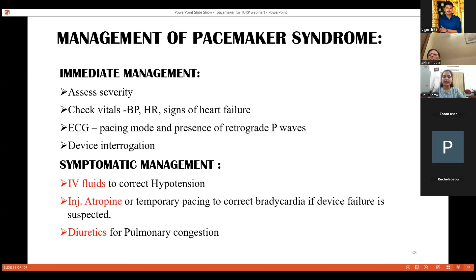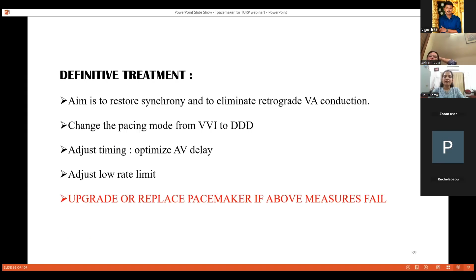Coming to definitive treatment, the aim is to restore synchrony and to eliminate retrograde VA conduction. We have to change the pacing mode from VVI to DDD. We have to adjust timing and optimize AV delay. We have to adjust the low rate limit also. If all the above measures fail, then we have to upgrade or replace the pacemaker.